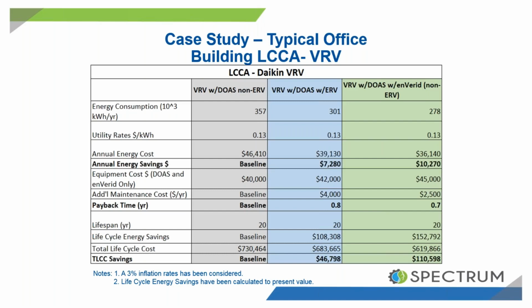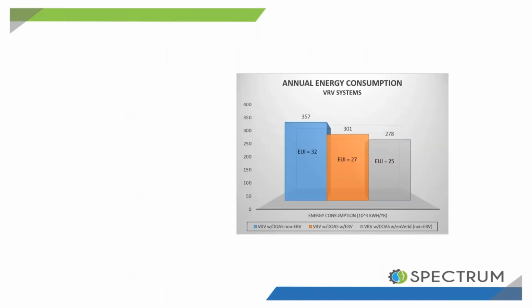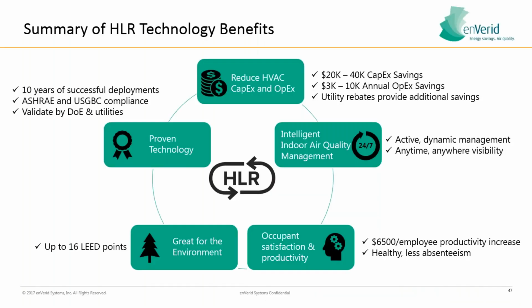Another example, so that was with a VAV. With a VRV system, you're looking at a total lifetime cost savings differential of almost double over a 20-year period, and essentially an equipment cost of a marginal increase here with enVerid versus the ERV. So marginal equipment costs, but you essentially make that up immediately in the annual energy savings achieved as well. So 7,000 versus 10,000 with enVerid here. And that enables you to get an EUI score of 25, which many regions have a mandatory requirement of 50 or below. Others are more stringent, but to have an EUI score of 25 is absolutely phenomenal, okay?